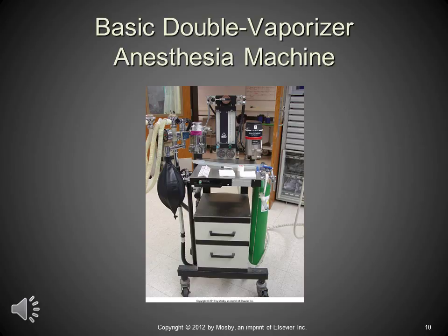But you can have 2 or 3 vaporizers. And it's common when you get an anesthesia machine from a human hospital that you'll have maybe a Sevo, an ISO, and a desflurane vaporizer on it. You know, enflurane you don't find much anymore. But yeah, you can have 2 different vaporizers on there, and if you're in the ISO mood one day, you use ISO. If you're in the Sevo mood one day, you use Sevo.